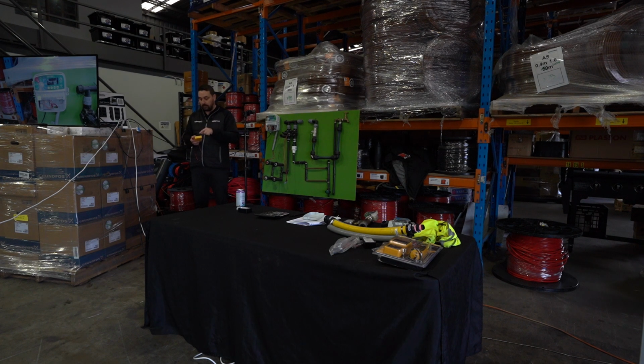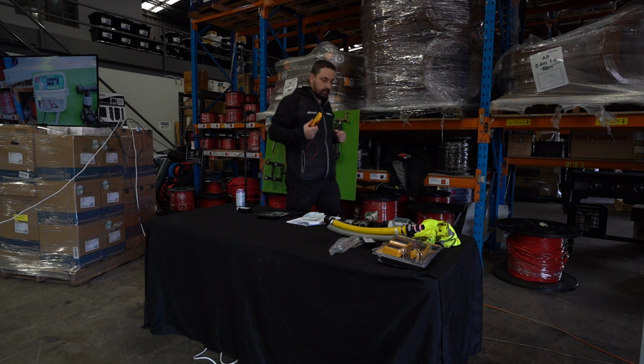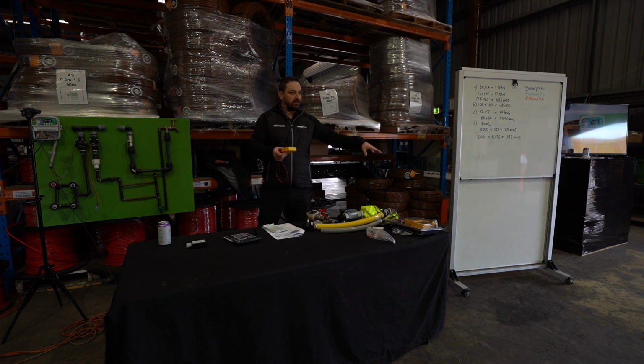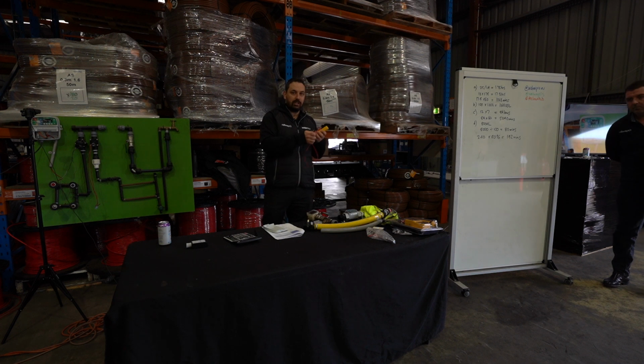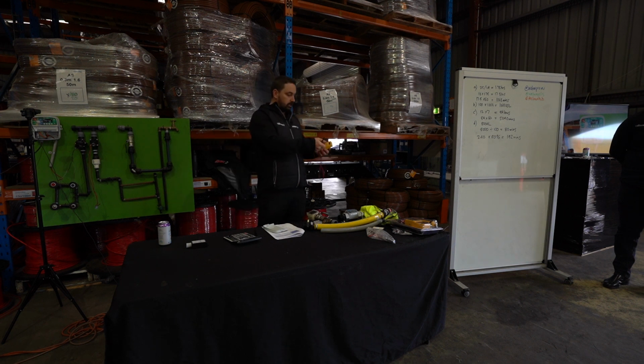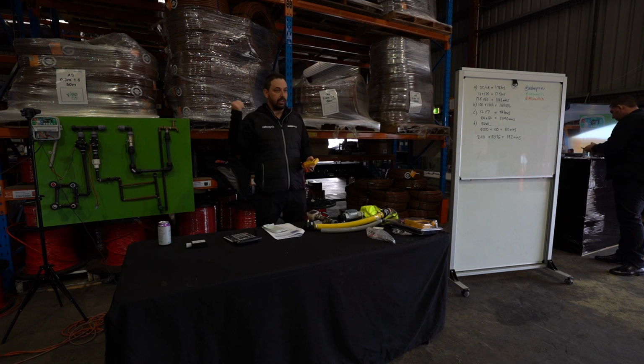That's really basic. I guess for me, the ohms reading on a cable is something that's so simple, but you can do it without having to go to a valve box and dig it up and undo things. You just go up to the station, and someone tells you, oh, station 5's not working. I used to go up there straight away, look at it, yeah, it's wired in, okay, turn this on to Omega, go across station 5 and it says overload, and I'm like, oh, the coil's dead. Do you know what I mean? And straight away you go to your ute, grab a coil and 2 wire joiners, and you're out of there in 20 minutes and it's sorted.